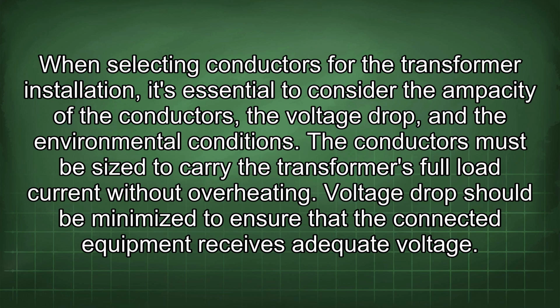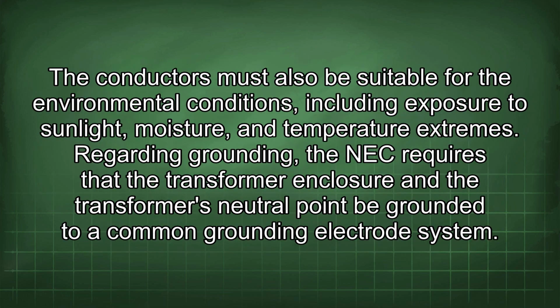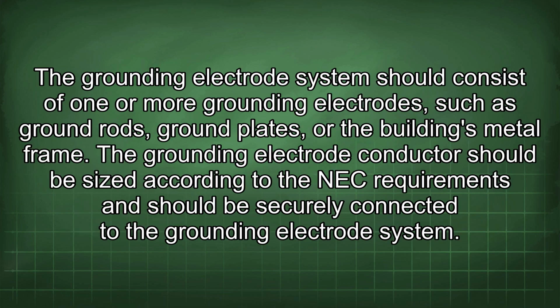Voltage drop should be minimized to ensure that the connected equipment receives adequate voltage. The conductors must also be suitable for the environmental conditions, including exposure to sunlight, moisture, and temperature extremes. Regarding grounding, the NEC requires that the transformer enclosure and the transformer's neutral point be grounded to a common grounding electrode system. The grounding electrode system should consist of one or more grounding electrodes, such as ground rods, ground plates, or the building's metal frame.